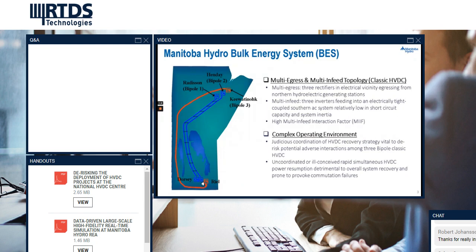The addition of Bipole 3 HVDC to the existing Bipole 1 and 2 HVDC system features an electrically coupled three-bipole multi-egress and multi-infeed topology. In the north, three rectifier stations egress from the northern collector system where a heavy concentration of hydroelectric generation is present. In the south, three inverter stations feed into a common interconnected AC system with relatively weak strength in short circuit capacity and system inertia.